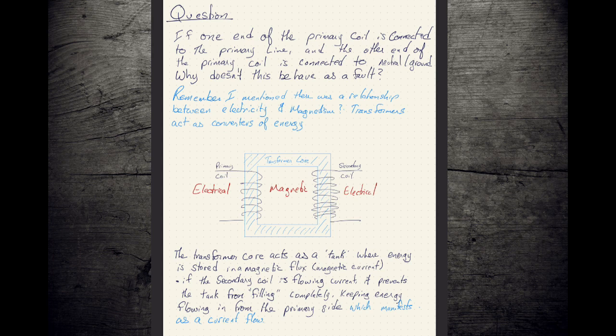If you think about this like a water tank, really, you could have like a 4-inch main coming in, and you've got a great big storage tank full of water, and then maybe you've got a 1-inch feed line coming out of that tank. And so when the tank is empty, that line is going to be flowing like crazy. So when there isn't that magnetic circuit set up, yeah, this coil does look a lot like a short circuit. Really, really high currents are going to flow.